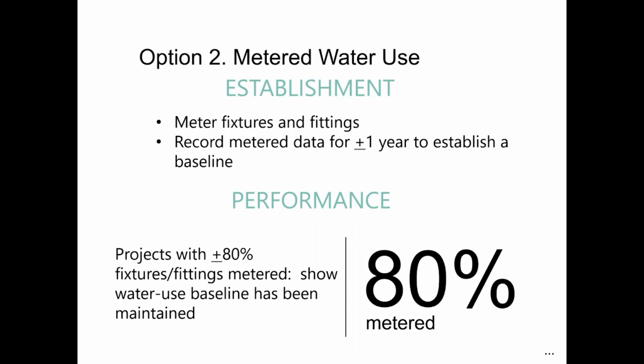If you have meters already installed in your building, your baseline can be set from your own building rather than just a generic code fixture. You want to record that meter data for a year or more to establish a baseline, and this is one of the reasons your building needs to be in operation for a year before you can go for O&M. So to even consider this option, you have to have those meters in place, and 80% or more of those fixtures need to be metered to show that water use baseline.